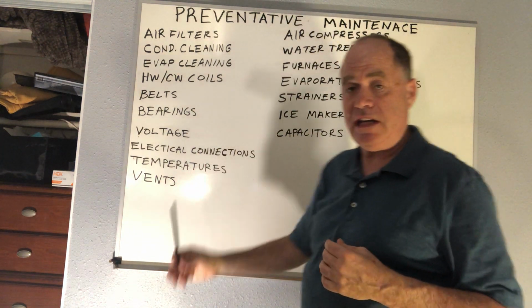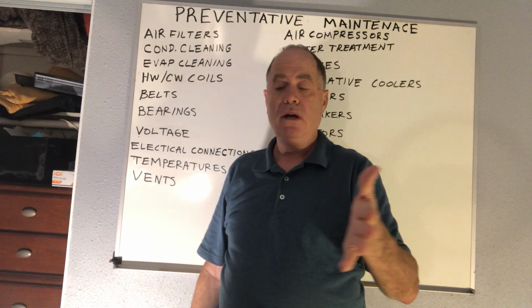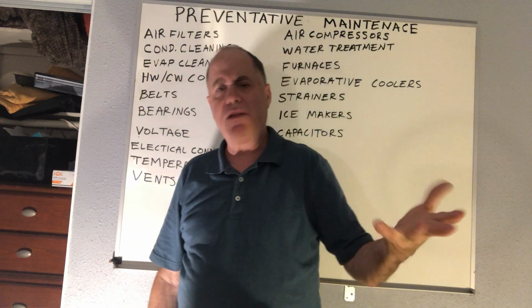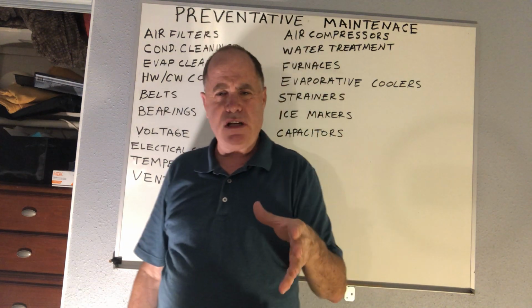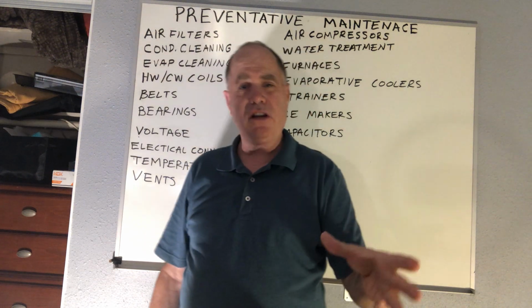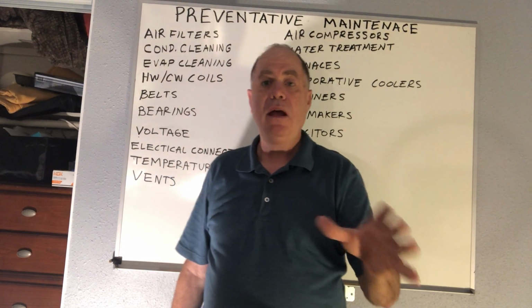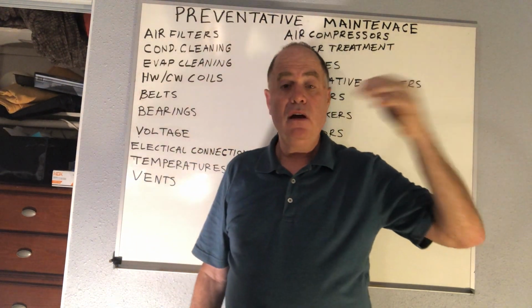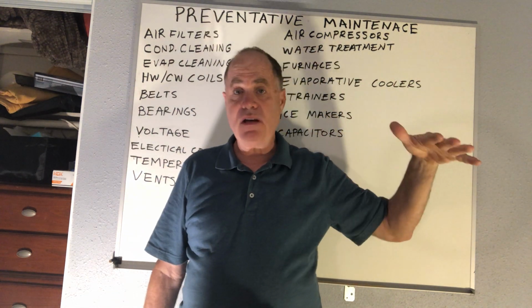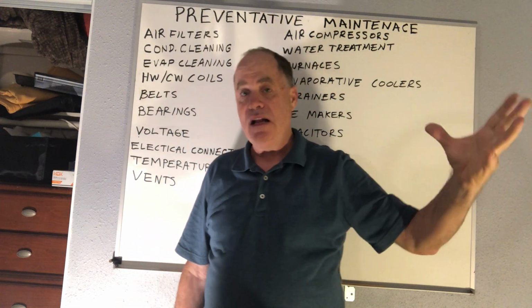Okay, let's talk about condenser cleaning. That's important, and the most important time, if you only had 1 month a year to clean condensers or have a program for that, it would be right before the first heat wave, or you might think like April, because if you have a pretty dirty air-cooled condenser and that system, whether it's refrigeration or air conditioning, has to run in February, it's going to run okay. It's not going to break down. However, that same system in August will break down. So getting the condenser as clean as possible for air conditioning before the summer so that it can get through that very hot summer when the condenser's outside in a hot environment is important.